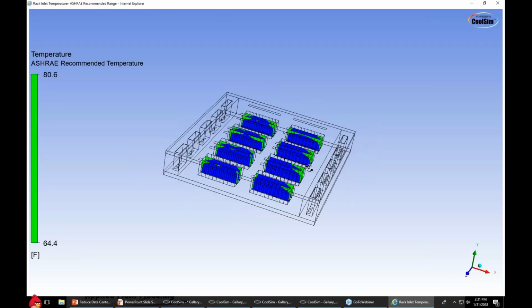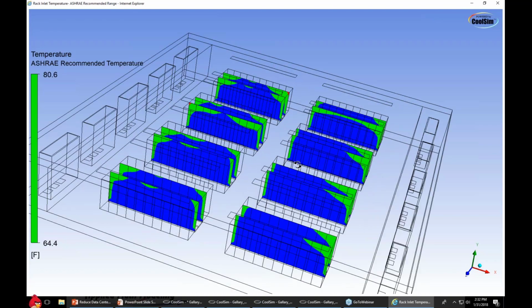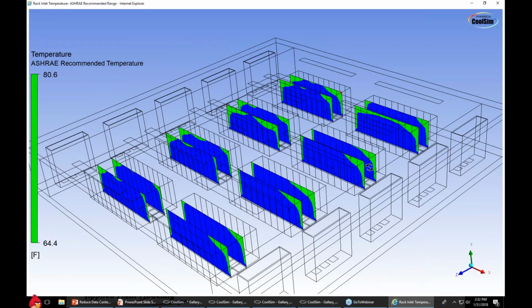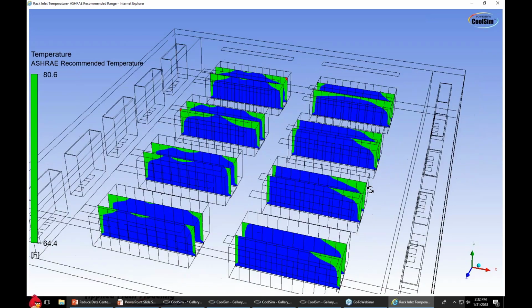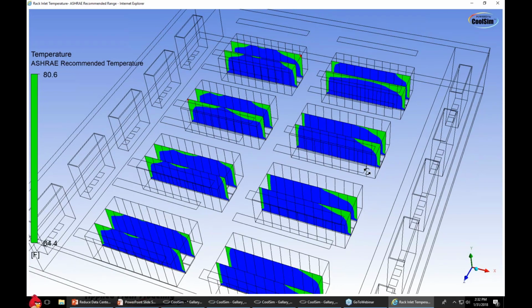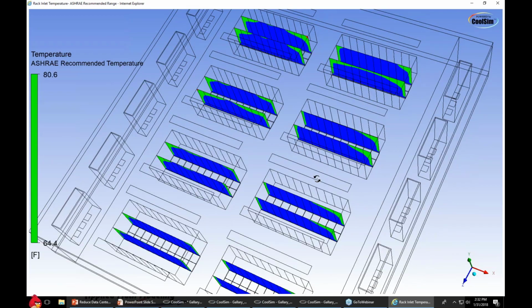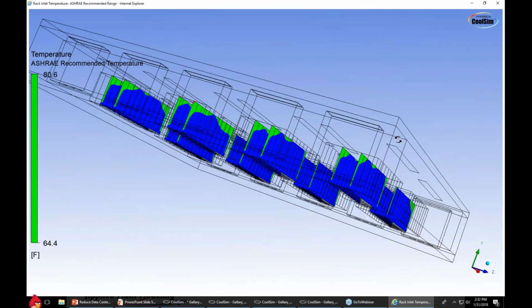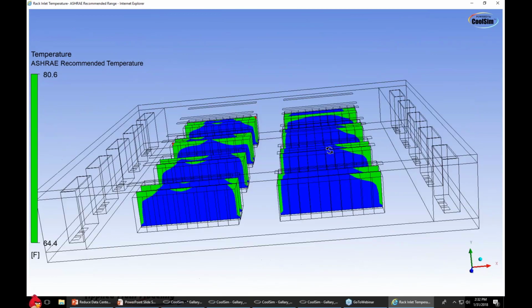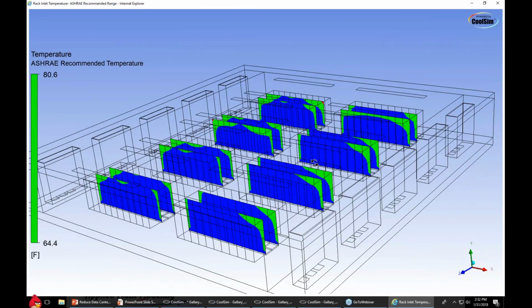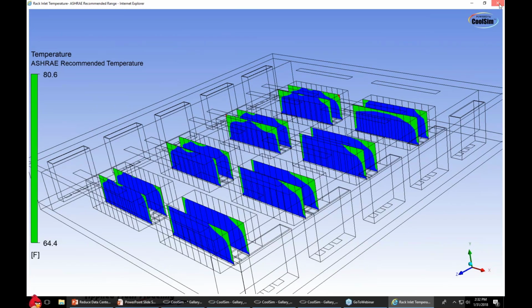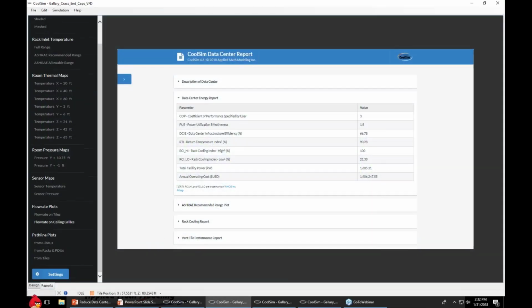You see we've got some, again, and this is a design that only has end caps on it. The reason I did this is because you can be quite effective with this design. I am not always an advocate of full containment. We could have put a full contained box around that, but there are issues with full containment, such as pressure, that you get into with these that this system eliminates. There is no pressure issue here because it's open. And furthermore, it's inexpensive.